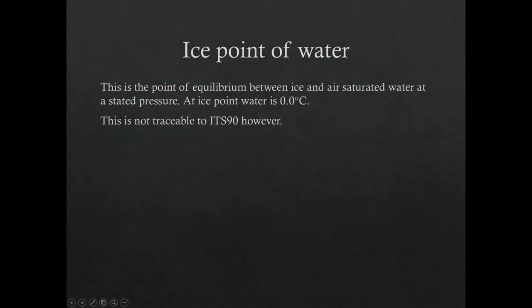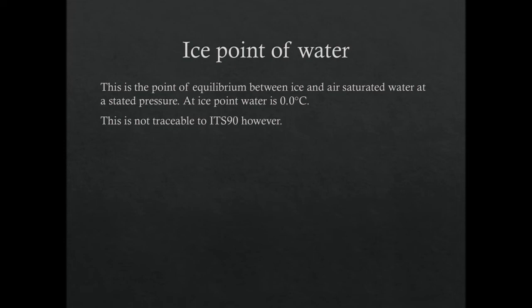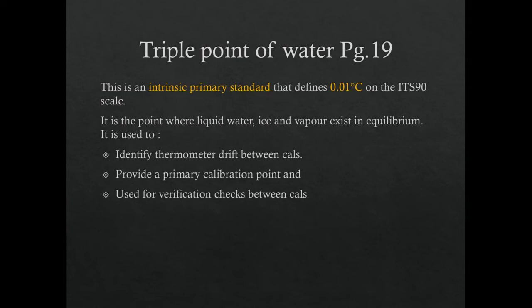The ice point of water is similar but technically between ice and air-saturated water at a stated pressure — close to zero but not quite. The triple point at 0.01°C is actually the primary reference per ITS-90, while the ice point is stated at 0.0°C and is not traceable to ITS-90. The triple point involves all three states simultaneously, which is likely why it is the defined standard.